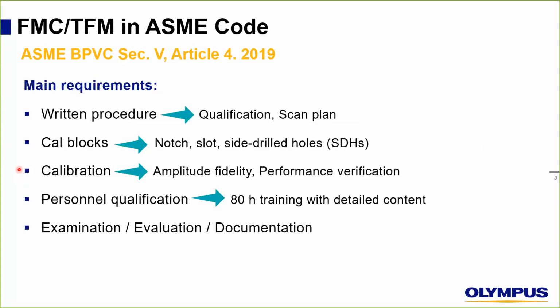So, a written procedure, of course, that talks about qualification and scan plan. The cal blocks, and this is actually different from the cal blocks of phased array. So we have a notch, a slot, this is the new stuff, and side drilled holes. Calibration that talks about amplitude fidelity, this is new as well. Performance verification, this is also different from phased array. Personnel qualification: the ASME code requires 80 hours of training with detailed content, and then we have examination, evaluation, documentation, etc. The main topics that will be discussed in the next sessions are underlined here: scan plan, cal blocks, amplitude fidelity, performance verification, and personnel qualification.